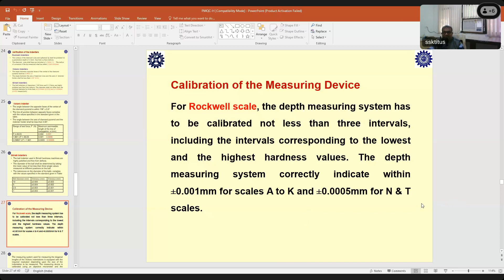So you have to calibrate the measuring system for the entire range. It should be within plus minus 0.0005 for this, and plus minus 0.001 mm accuracy should be there.